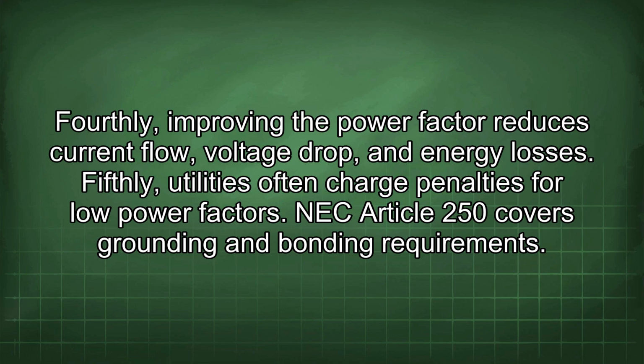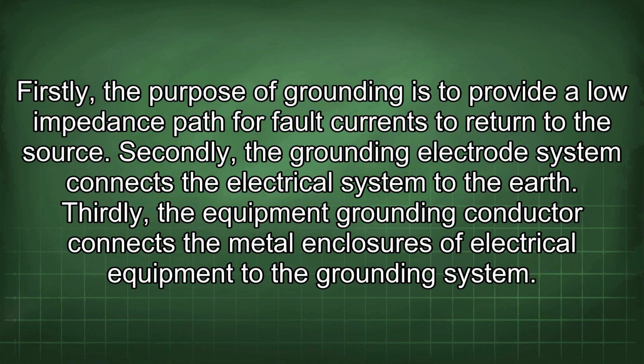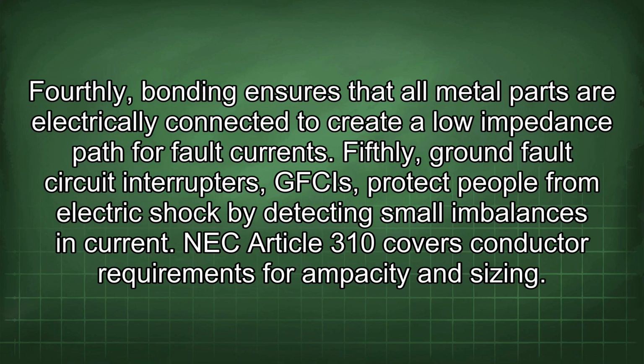NEC Article 250 covers grounding and bonding requirements. Firstly, the purpose of grounding is to provide a low impedance path for fault currents to return to the source. Secondly, the grounding electrode system connects the electrical system to the earth. Thirdly, the equipment grounding conductor connects the metal enclosures of the electrical equipment to the grounding system. Fourthly, bonding ensures that all metal parts are electrically connected to create a low impedance path for fault currents. Fifthly, ground fault circuit interrupters, GFCIs, protect people from electric shock by detecting small imbalances in current.